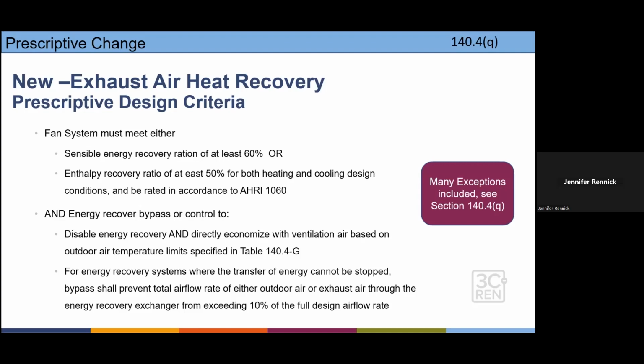So a lot of these requirements now are to dictate that your heat recovery system has to have a certain efficiency in the first place, and the fans have to meet certain efficiencies, and you have to do other things with the controls to make these work. And another key point about those heat recovery ventilators is that the efficiency really makes a difference in how well your building complies for Title 24. And so if you're not passing and the report bumps up that efficiency, then you're passing, but then you've got to make sure the actual equipment installed is in alignment with your Title 24 report. And I think a lot of folks aren't necessarily used to looking for that number for the efficiency rating of the unit itself for heat recovery.